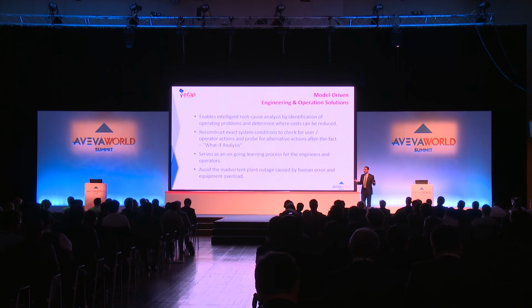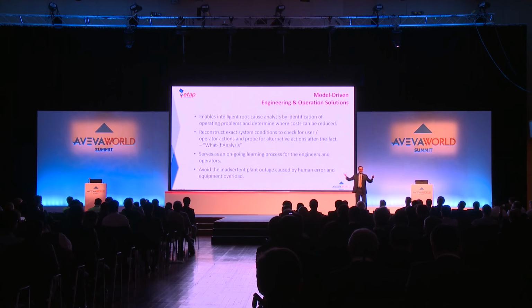This compressor doesn't run or start every day, it's online and producing. So for this operator to see what will happen if everything was running while this compressor was off, he wants to virtually simulate the start of this compressor. He can take a snapshot of the system, get the exact level of generation, loading, the topology of the system, the statuses of breakers and switches, whatever is in the system, and start that compressor to find out if there's going to be an issue, an under voltage, a brownout, and then take that action once he's validated it using a real-time model connected to the metering equipment.